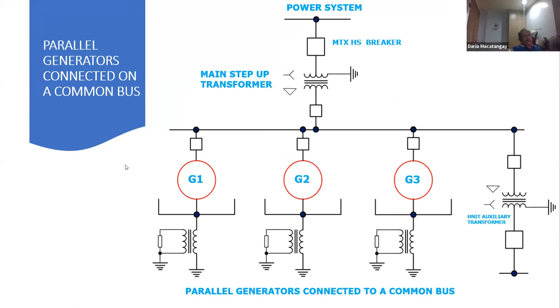All right, there's another configuration here. This is typical in industrial plants. You have several generators connected on the same bus, okay? You can see here that they are connected in parallel with unit transformers on the same bus, with one common auxiliary transformer. There are some issues here associated with the ground fault. It's difficult to coordinate the protection here because they are connected in parallel, so there are special arrangements to implement protection for parallel generators.